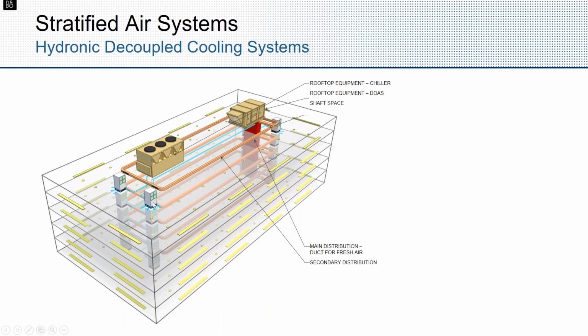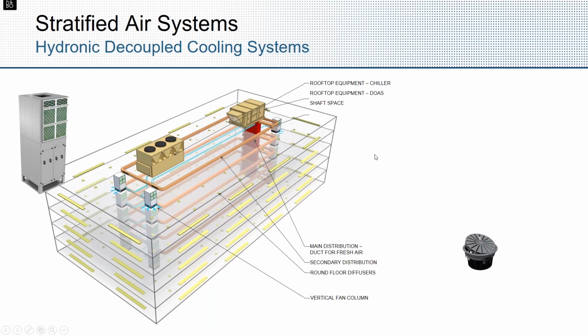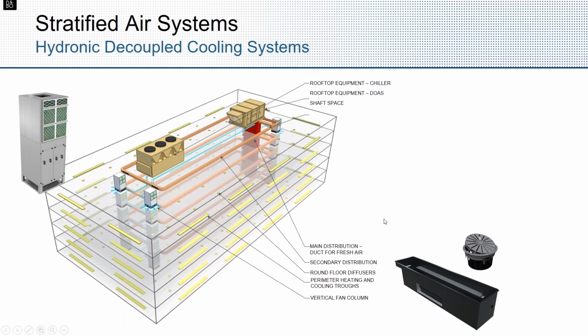Here's an example of the decoupled version of the cooling system for this underfloor air, where we've got air towers at each corner of the core, and they're discharging downwards and pressurizing the underfloor plenum. So the outside air is being distributed and then ducted either to the top or just supplying into the mechanical rooms that are out of the core and into the tenant space. And then that's handling your sensible cooling through the cooling coil and conditioning the underfloor air plenum. Then we've got manual round floor diffusers located throughout. Again, very simple, elegant design, pretty much the same diffuser and face placed evenly throughout, giving occupants control of their thermal comfort and their air supply volume.